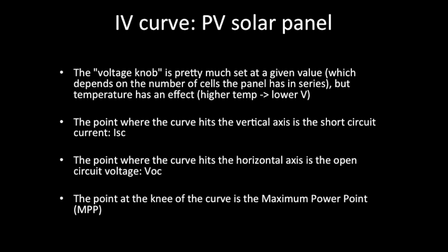That's a little counterintuitive to some people, but a higher temperature panel reduces your power. Ironically, the more it's in the sun, the higher temperature it gets, and actually the lower the power is. The point where the curve hits the vertical axis is called the short circuit current, ISC. The point where the curve hits the horizontal axis is the open circuit voltage, VOC. And the point at the knee of the curve is the maximum power point.